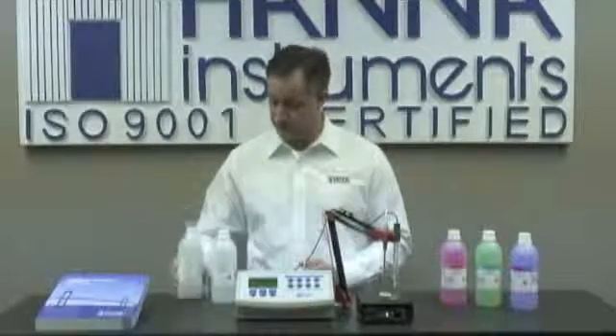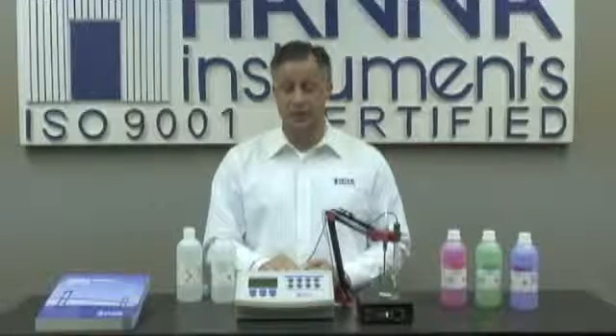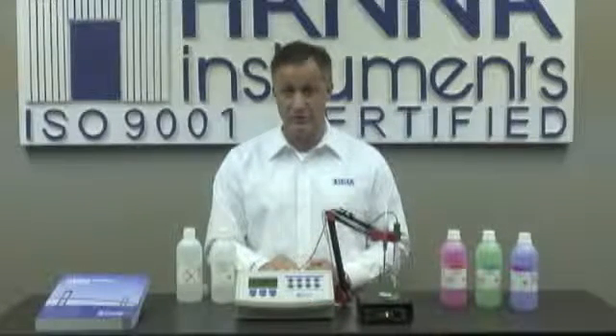Another note, if your instrument ever displays clean electrode, it's an indication that you could have a dirty probe. In that case, we offer application-specific cleaning solution. Today's demonstration was on a 3222, which is a 2-channel meter, and again, it's pH, millivolt, and ISE. Today's demonstration was on setup and calibration for pH. We have a separate video for an ISE, so if you're interested in viewing the ISE portion, please watch our separate video.